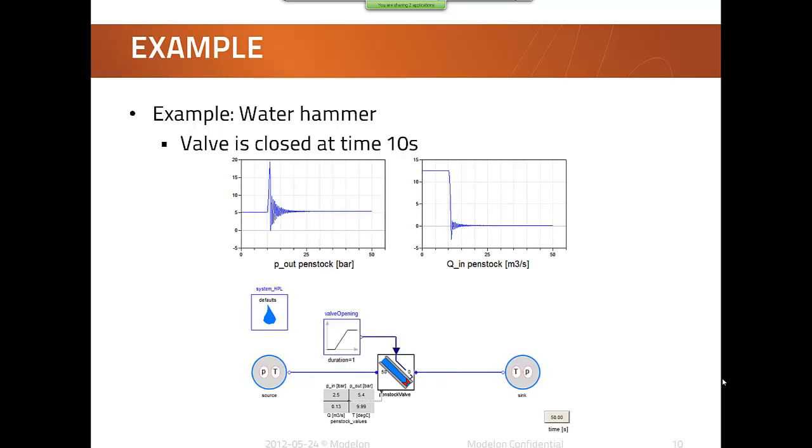Another quite famous thing is the water hammer effect. So this is more or less that if you have water that's moving and then you suddenly close a valve, then we will have more or less like shock waves in the system. And this is something they call water hammer, and they usually have a really high frequency. So this example demonstrates this with closing the valve at time 10 seconds. Then you will see that the pressure goes up and it will start to oscillate. And this is only to show that this library can handle this water hammer effect.